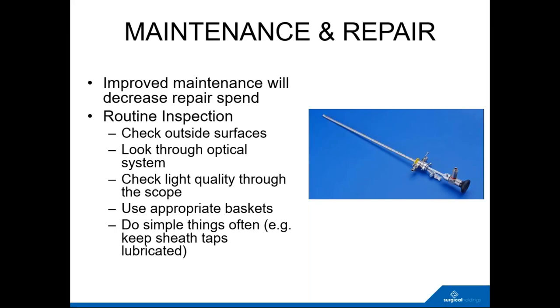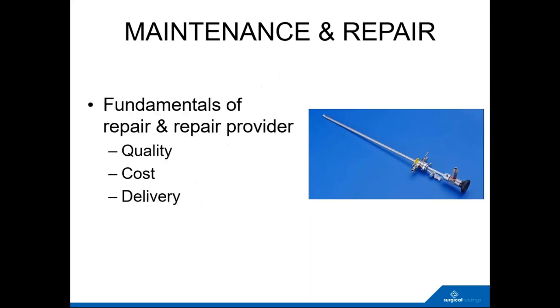Well, that's actually a picture. That's a cystoscope in the picture on the right hand side. And I said do simple things often. Look at the instructions for use from your manufacturers, and these taps here, for example, keep them lubricated. Otherwise, they'll just leak, and so the urologist in that situation is getting very wet, or a very wet floor. It's a wet procedure anyway, but what you don't want is leaking taps. So simple care and maintenance can really improve and prevent repairs.